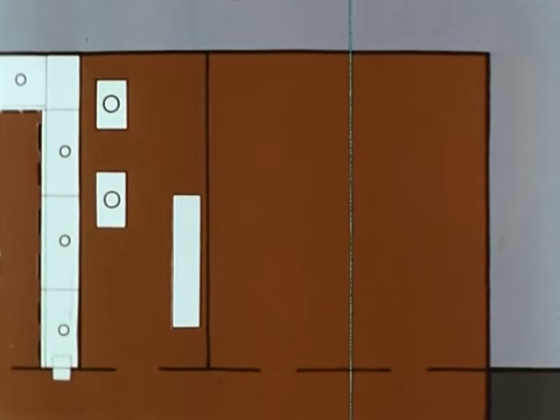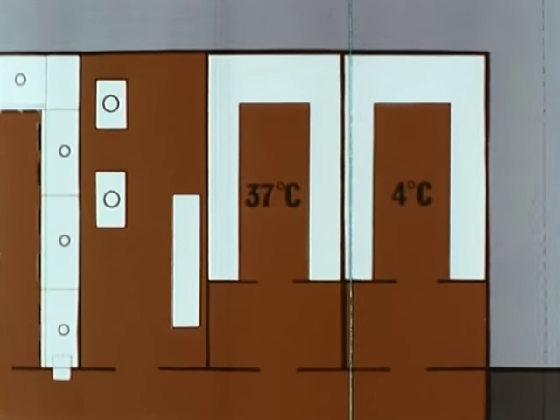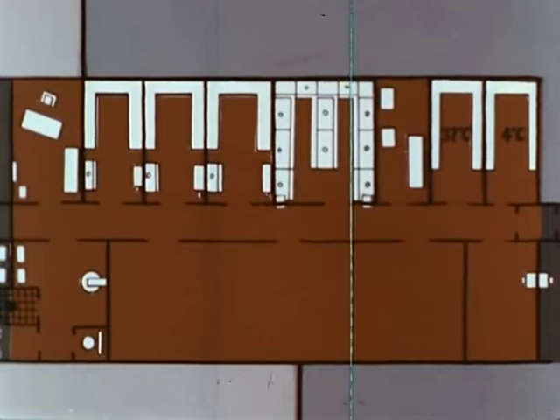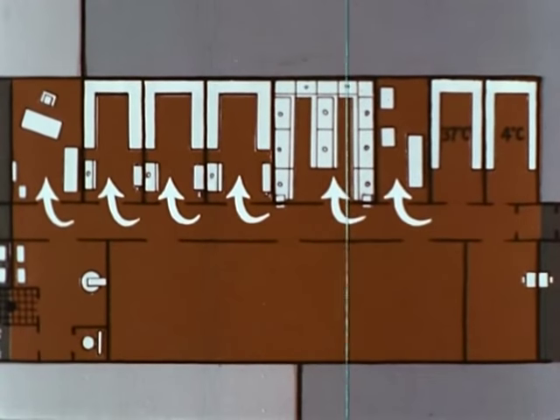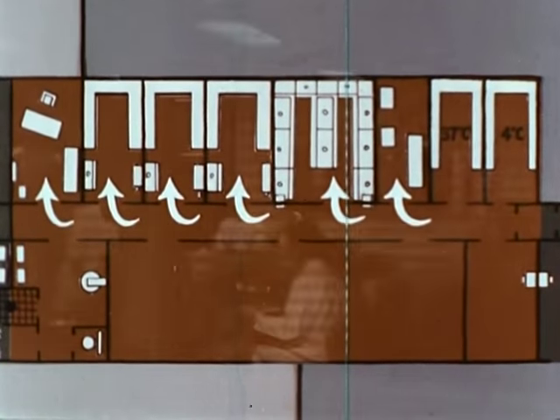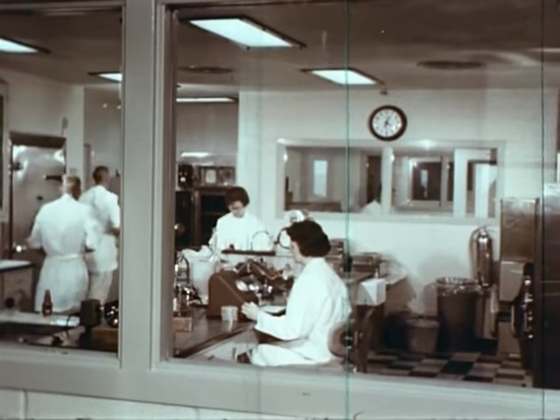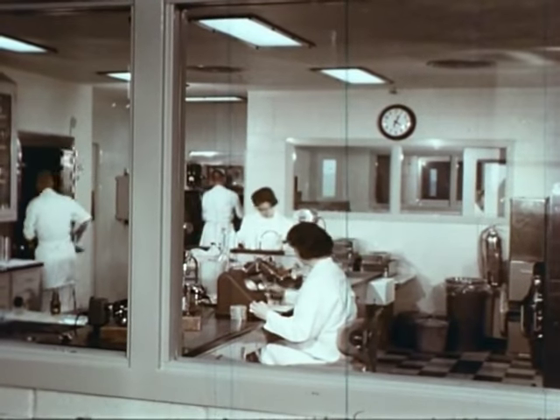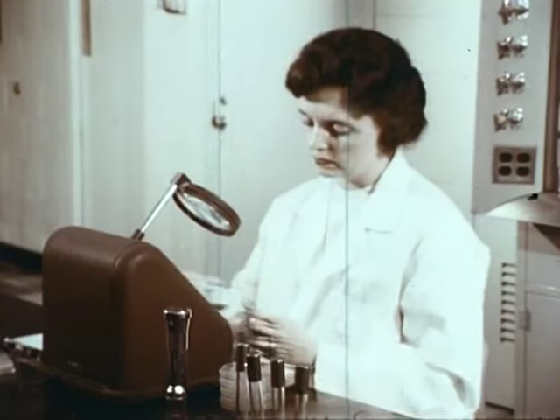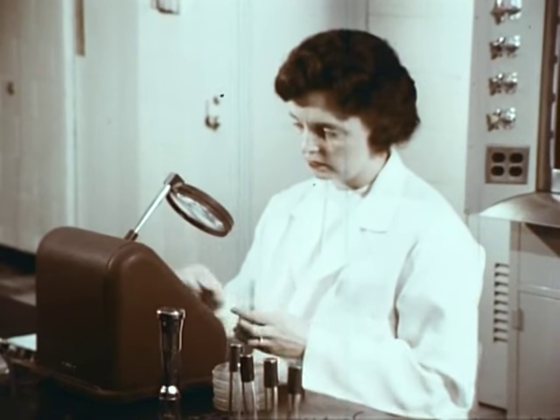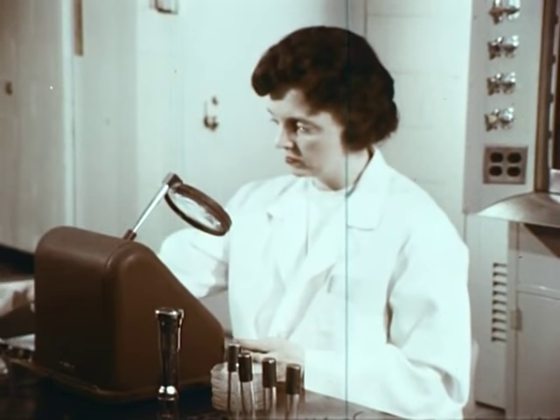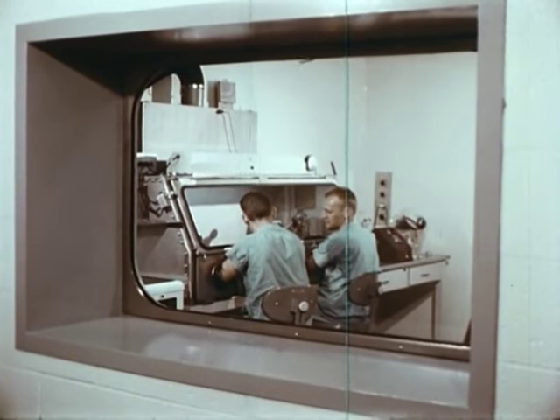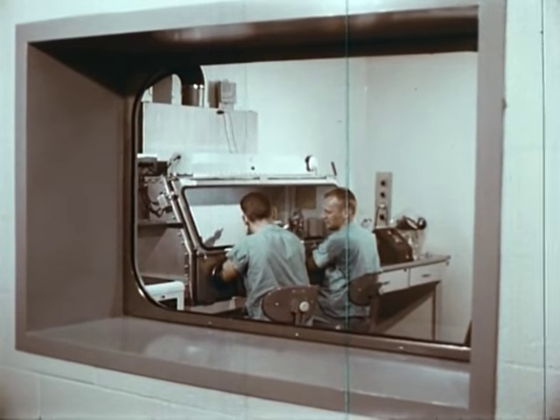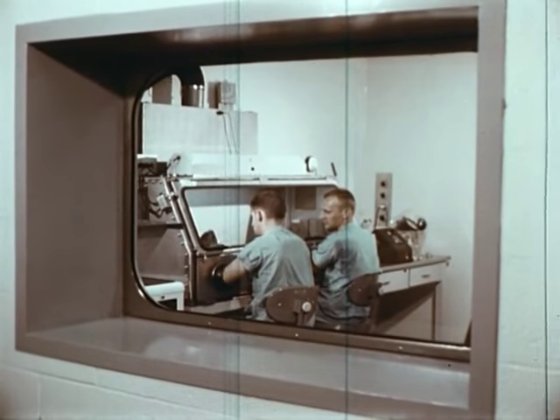Other common features usually found in this research area are an instrument room for centrifuges and other apparatus, and constant temperature rooms for incubation and refrigeration. The hallway with air pressure positive to the lab rooms provides additional room-to-room separation. Let's examine some containment features found in this area, remembering that this is where the bulk of research and diagnostic work is done. The laboratory zone should be maintained at an air pressure negative to the clean zone. The lab rooms themselves should have an air pressure negative to the adjoining halls, and the ventilated cabinets should be negative to the rooms.